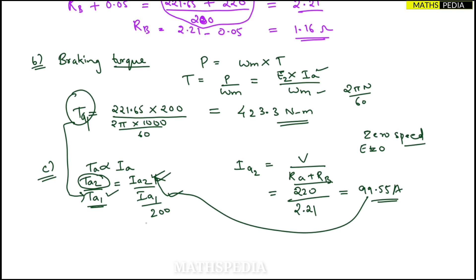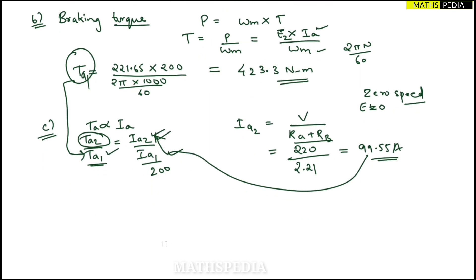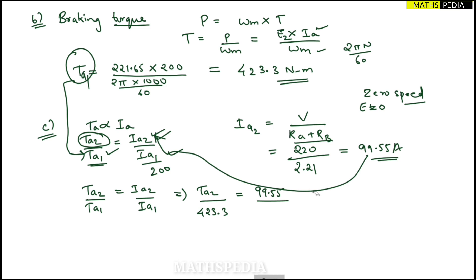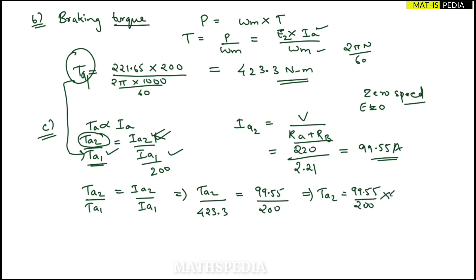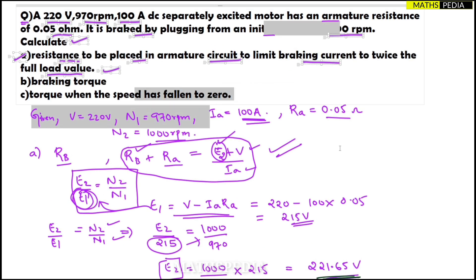Now substituting all values: Ta2 / 423.3 = 99.55 / 200. Therefore Ta2 = (99.55 / 200) × 423.3 = 210.7 Newton meter. This is the braking torque when the speed has fallen to zero. The entire problem is now complete.